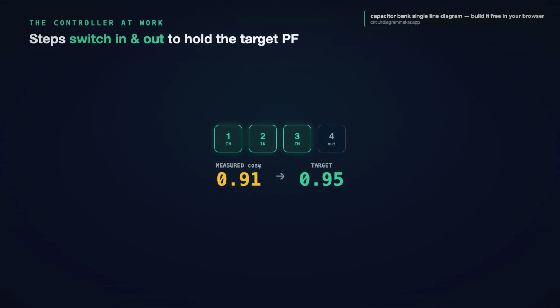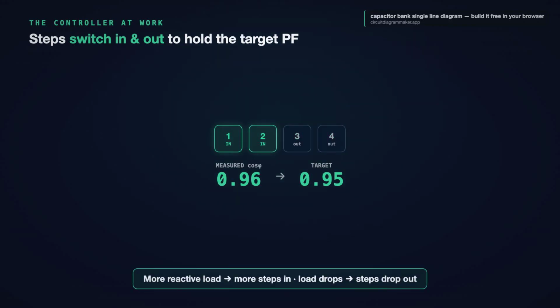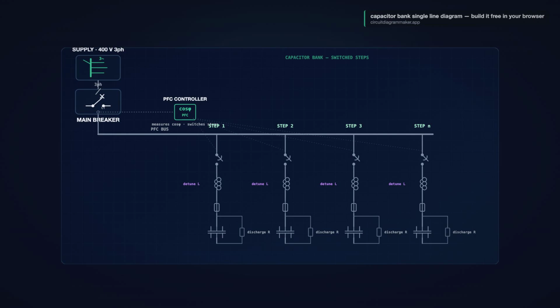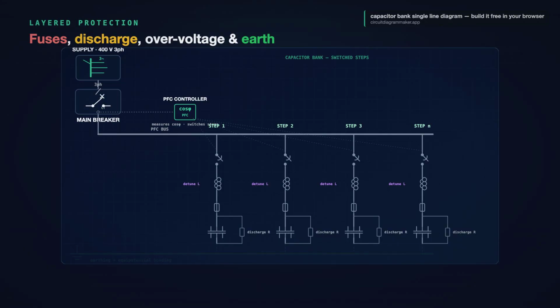This is what makes an automatic bank different from a fixed one. At light load, the power factor is poor, say 0.78, and the controller has only a step or 2 in. As the plant loads up and draws more reactive power, the controller closes more step contactors, bringing more kVAr online, and the measured power factor climbs toward the target. Then the shift ends, the load falls away, and the controller drops steps back out, so the bank never overcorrects into a leading power factor. Steps in as reactive demand rises, steps out as it falls. That constant balancing act, holding the line at the target, is the controller's whole day.